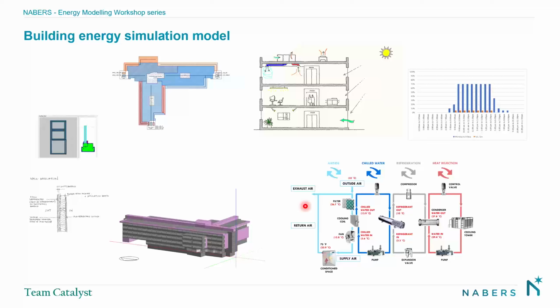Well, when you sized it, say you had 1,000 kilowatts, but that's for the design day, when outside conditions are very warm and everything is assumed to be going flat out—all the occupants are there doing what they're doing, all the lights are on, all the equipment is running. By definition, you only need that for about 1% of the year, because that's what a design day is. Which means that for 99% of the year you don't need 1,000 kilowatts, and your control system needs to back off the air conditioning system efficiently for the rest of the year.